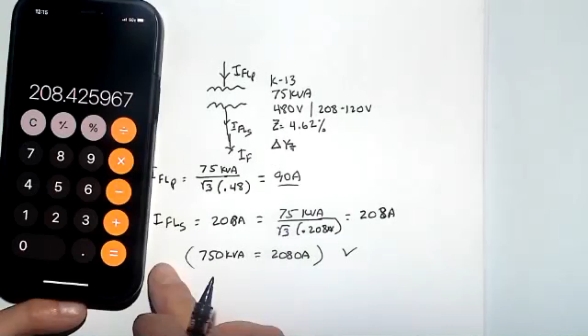What if I want to calculate my fault current here? I fault. So earlier I mentioned we just divide the full load amps by the impedance, but really what we're doing is we're calculating kVA short circuit. And kVA short circuit is kVA full load, which is our rating or rated, divided by the impedance in per unit. So in this case, it's 75 divided by 0.0462. That's 1623 kVA.